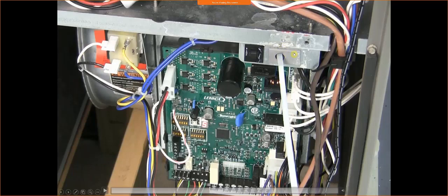If you take this door off and you're still trying to look for that trouble code, well, it's going to be like shutting power off to the system. If you don't have the capability of seeing or recalling the code, by pulling that door off, you're going to reset that code. So just keep that in mind. Before you take that door off, look through the peephole and see what kind of code we're getting, whether it's a digital or an LED display. That's going to help you identify what the problem is.